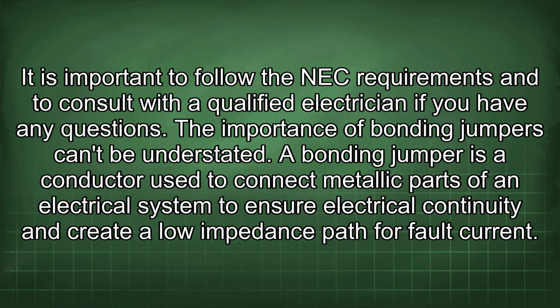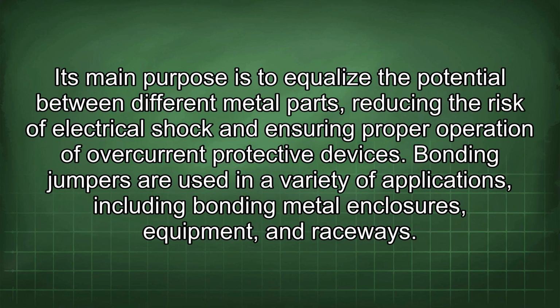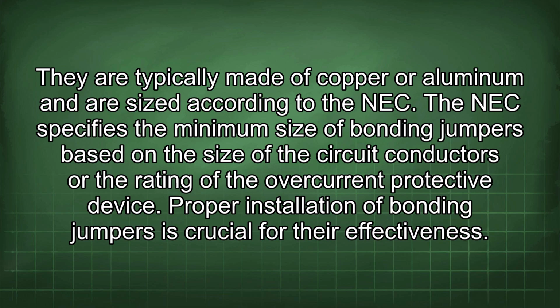A bonding jumper is a conductor used to connect metallic parts of an electrical system to ensure electrical continuity and create a low impedance path for fault current. Its main purpose is to equalize the potential between different metal parts, reducing the risk of electrical shock and ensuring proper operation of overcurrent protective devices. Bonding jumpers are used in a variety of applications, including bonding metal enclosures, equipment, and raceways. They are typically made of copper or aluminum and are sized according to the NEC. The NEC specifies the minimum size of bonding jumpers based on the size of the circuit conductors or the rating of the overcurrent protective device.